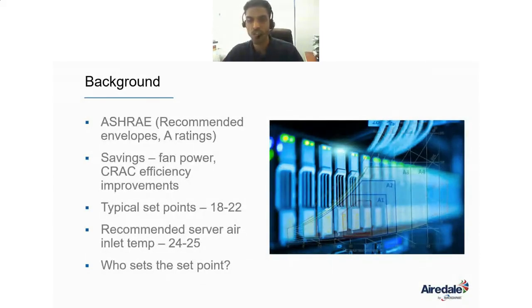What you usually see in a typical data center is a set point of 18 to 22 degrees C. Considering the ASHRAE limits, we recommend increasing the server inlet temperature up to 24 or 25 C, which allows you to increase the return air from a typical 18-22 to around 30, or between 30 and 35, and of course with containment.